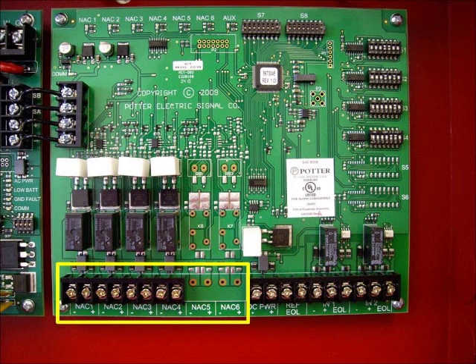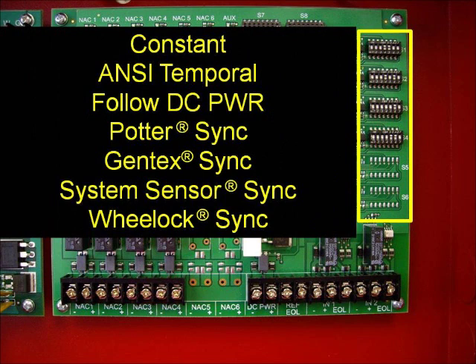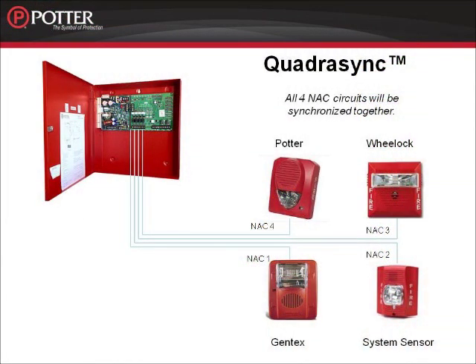We're now moving to the NAC outputs. You'll notice that I'm missing NACs 5 and 6 on my PSN 64 — if this were a PSN 106, NACs 5 and 6 would be there. Each NAC output is configured through the dip switches on the right. The NACs can be configured as constant power, ANSI Temporal pattern, they can follow the DC power characteristics, they can also be set up as Potter sync, Gentex sync, System Sensor sync, or Wheelock sync. Each circuit is configured independently. So for example, you could have one circuit of Potter, one circuit of Wheelock, one circuit of Gentex, and one circuit of System Sensor, and all of your strobe circuits would sync together. That's called Quadrasync.